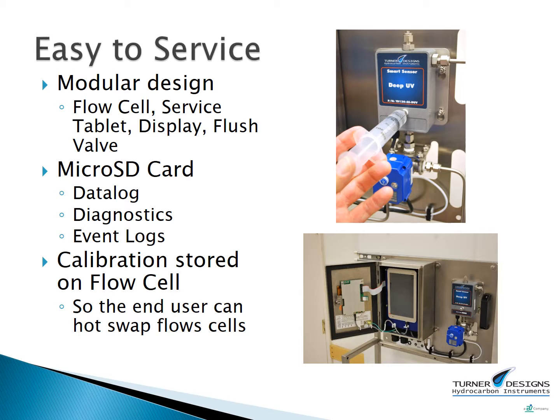Calibration data is stored on the flow cell itself. When the instrument is ordered with the factory calibration, a replacement flow cell can ship from the factory with the exact same calibration for easy hot swap as needed.